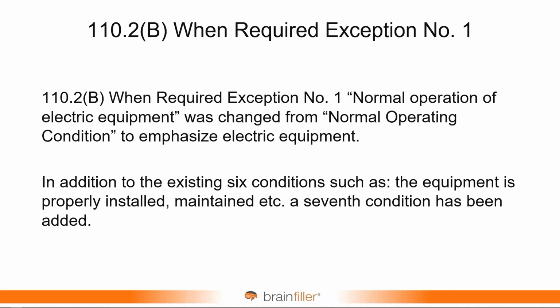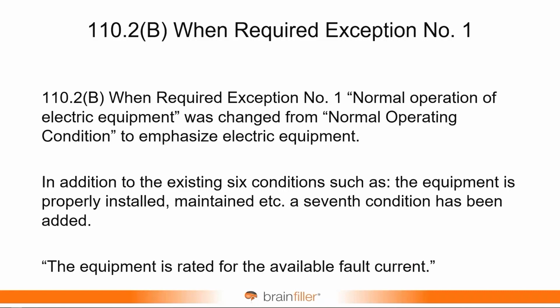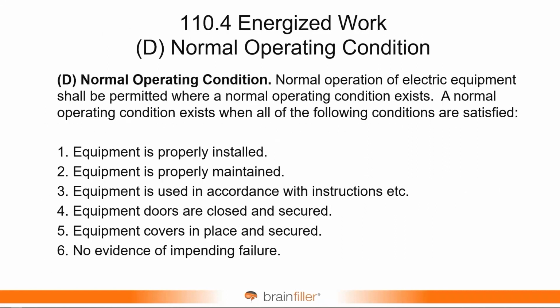There's been a 7th condition that's been added to this, and that is that the equipment is rated for the available fault current. So what we had previously in 2020, it was referred to as normal operating condition, and we had the 6 conditions that had to be satisfied. The equipment is properly installed, properly maintained, used in accordance with the instructions. The doors are closed and secured. The covers are all in place and secured. And there's no evidence of impending failure.